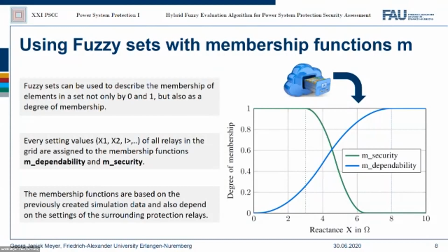It makes it possible to express independently the quality of each setting over a degree of belonging. The graphs of the membership functions are sigmoid functions, as shown in the picture right here. The function is based on the previously created simulation data and also depends on the settings of the surrounding protection relays. That means that the sigmoid functions of every setting look different for every relay, and that a change of setting values of one relay will therefore also lead to new membership functions of other relays.